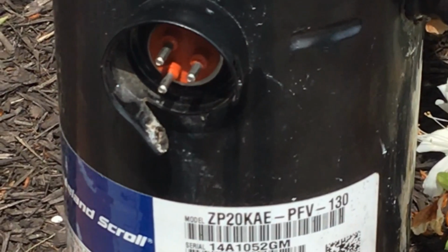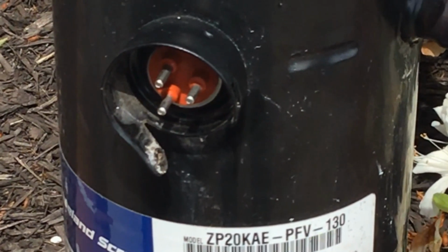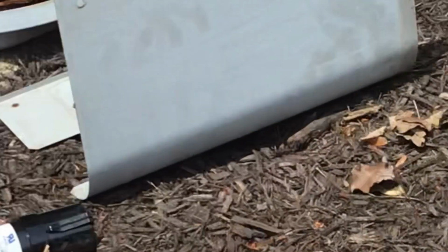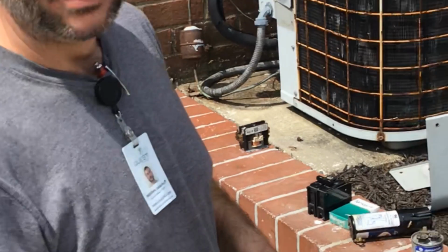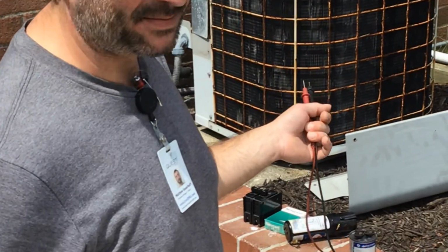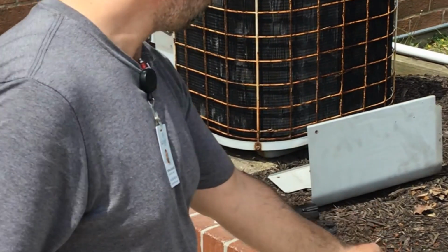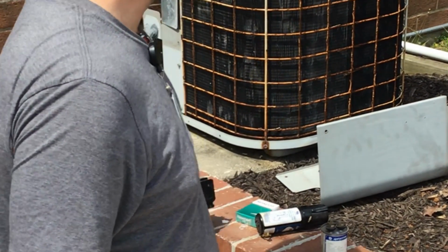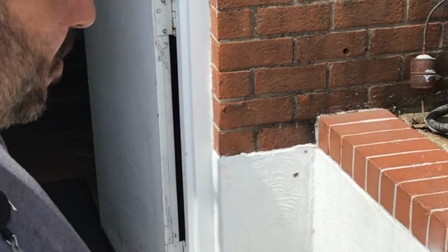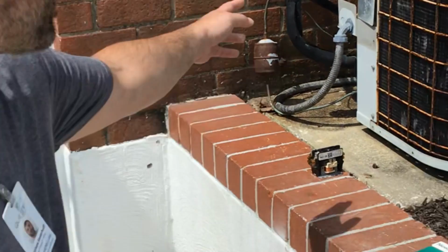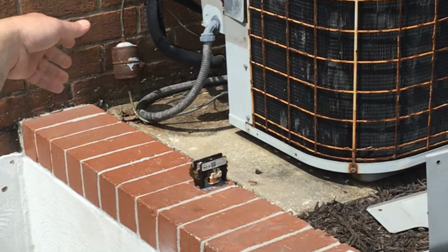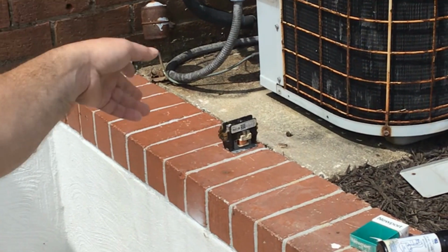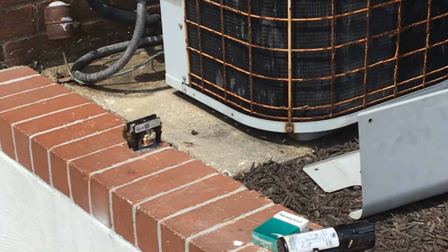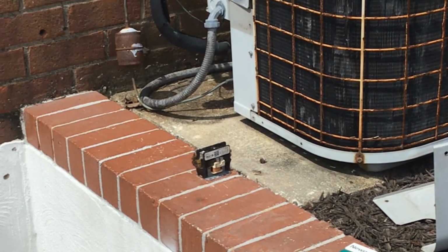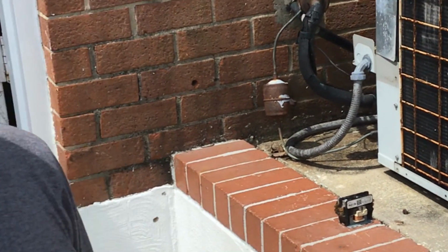Now it's covered: every component that utilizes 240 volts in your HVAC system, except 2. And it's pretty simple. One of the first checks, if you don't have power to your outside contactor on your line side, the next thing you want to check is your disconnect box. There's not one here. They're usually mounted on the brick.